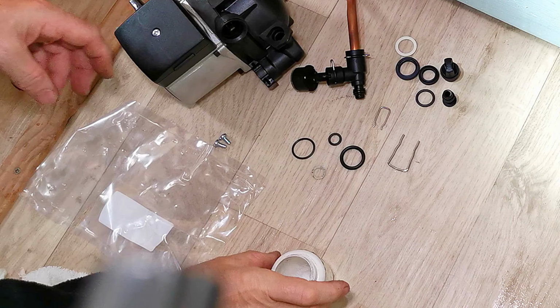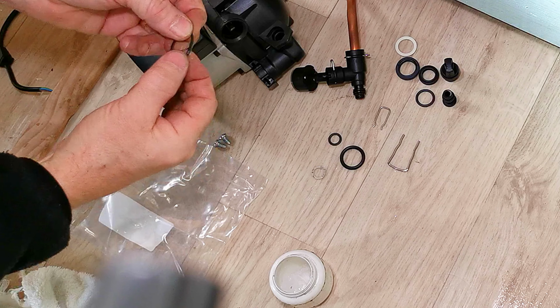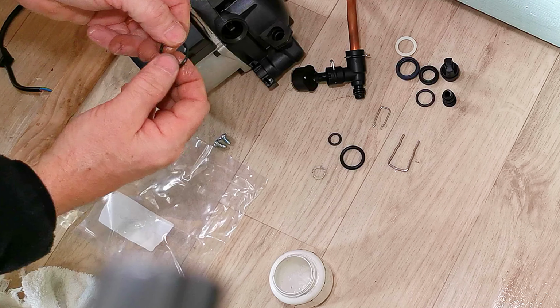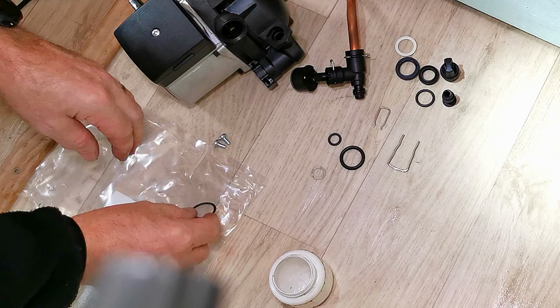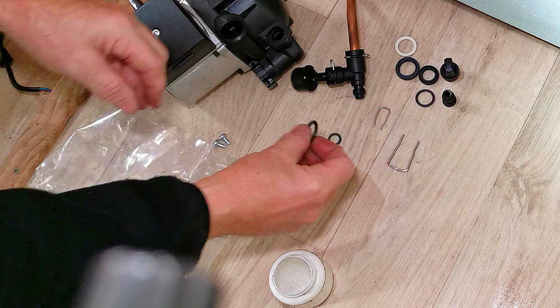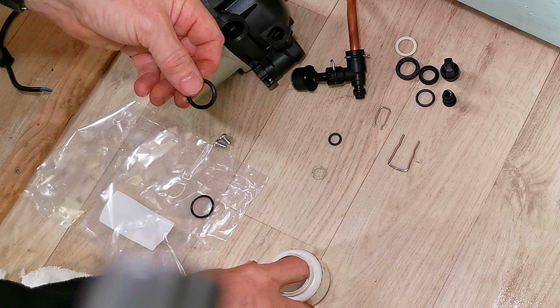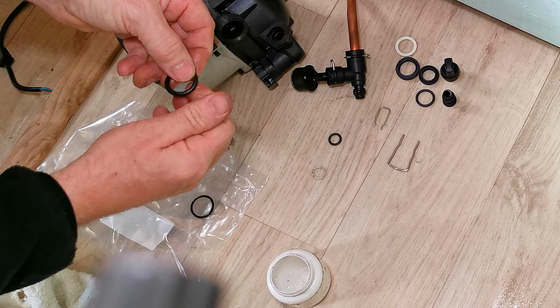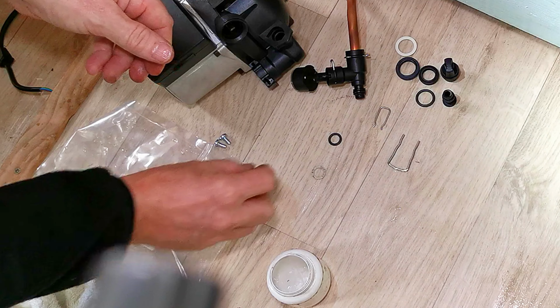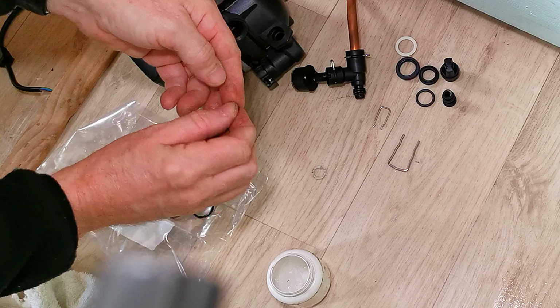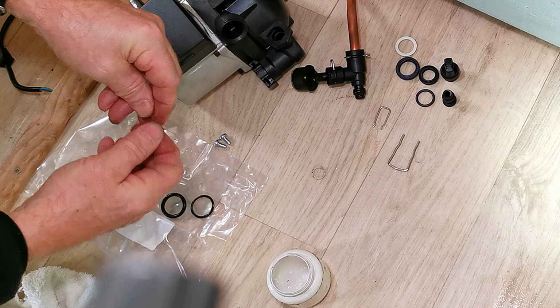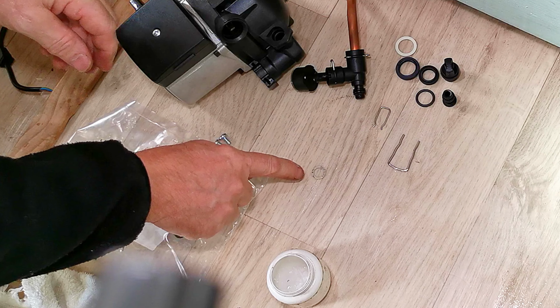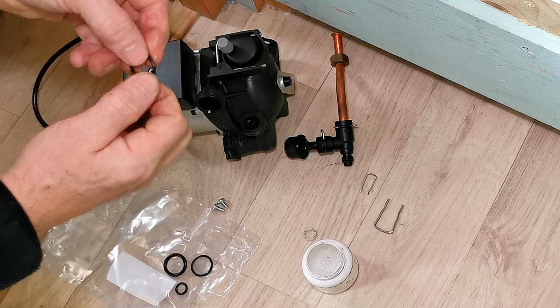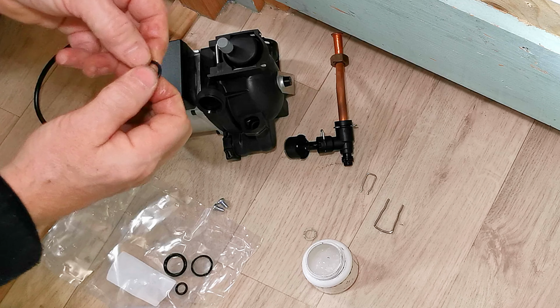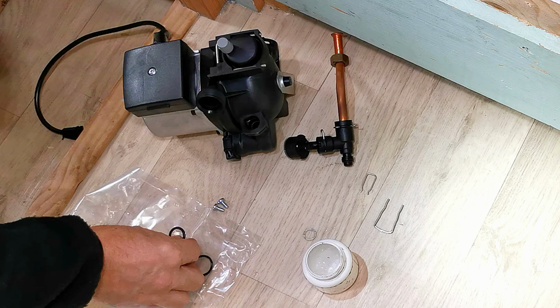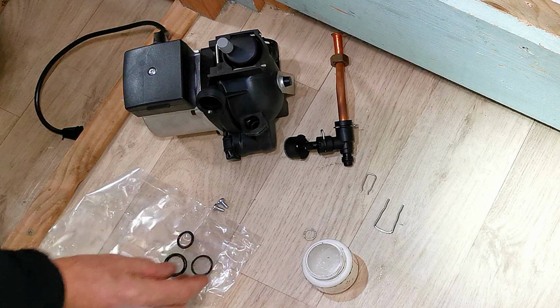So I'm now going to use some silicone grease and just grease up the O-rings which I'm going to be using. So there's a thin O-ring which goes onto the return pipe. We got the fatter one which goes onto the diverter valve. And there's a little O-ring which goes onto the pressure gauge. And the small fibre washer which goes onto the expansion pipe, I do not grease up at all. I nearly forgot there's the O-ring which goes onto the pressure relief valve. So there we are, we've got 4 O-rings to go back onto the pump.